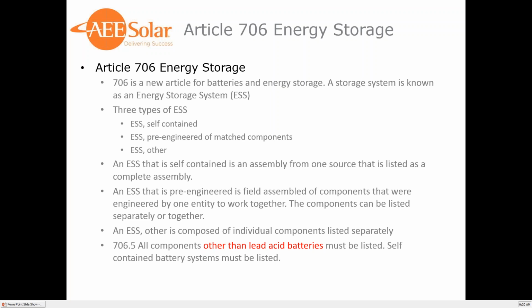An energy storage system other is composed of individual components listed separately. 706.5, all components other than lead acid batteries must be listed. Self-contained battery systems must be listed. So if you're using anything in the energy storage system other, they all must be UL recognized other than lead acid batteries. Lead acid batteries are only UL recognized and not listed. So they had to add that section in the code article.